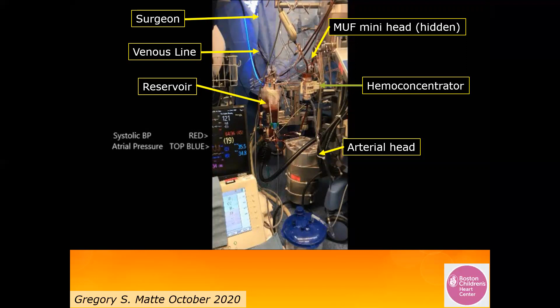And we will go through the 3 phases of MUF. The normovolemic phase, where the perfusionist essentially keeps the filling pressures the same using the reservoir volume. Then the hypovolemic phase, where hemoconcentration continues without volume replacement to a lower but safe blood pressure. And then the transfusion phase, when the venous cannula is taken out, placed under saline, and the residual MUF circuit volume is flushed forward to get the patient back to a normal volume status.